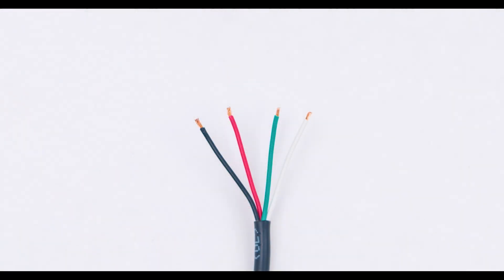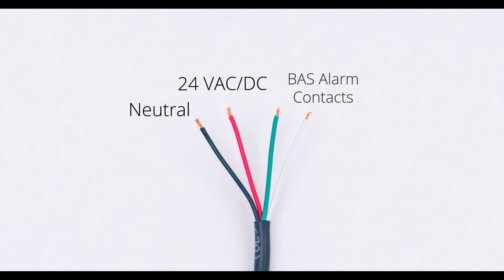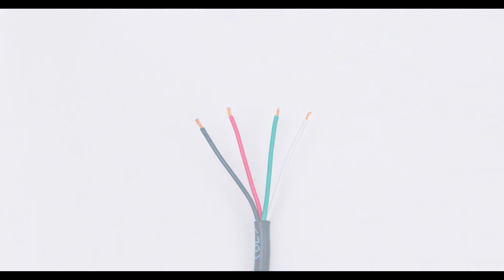When connecting the CI2 to the selected power source, black is neutral, red is nominal 24 volts, and white and green are dry alarm contacts.